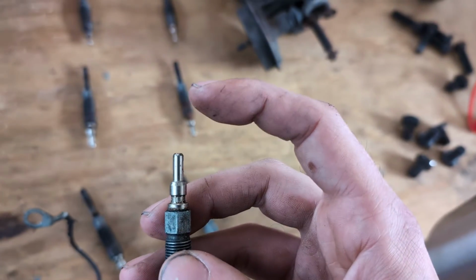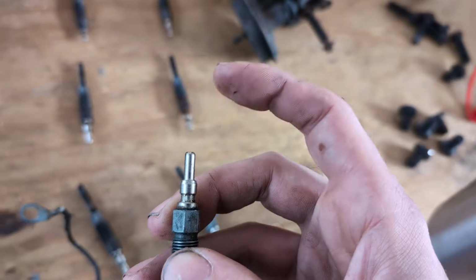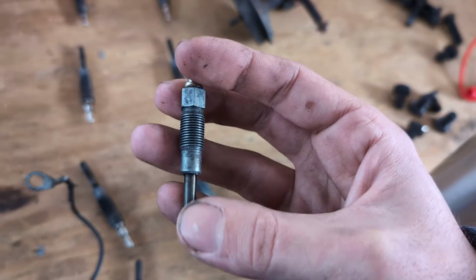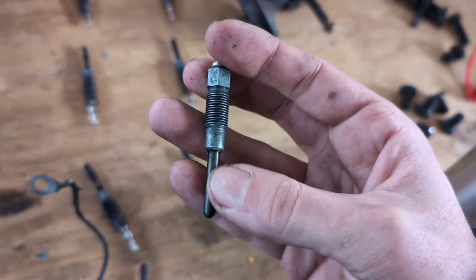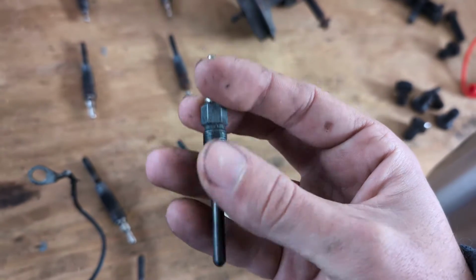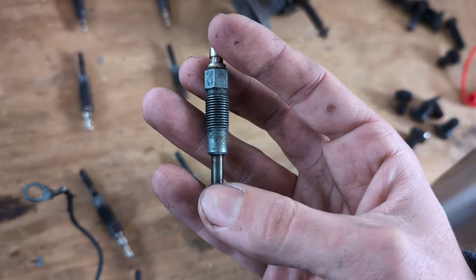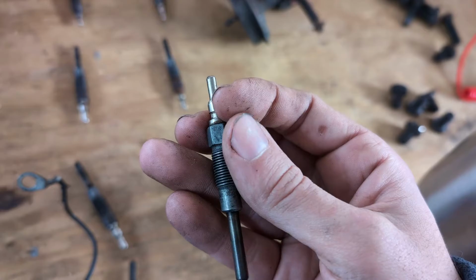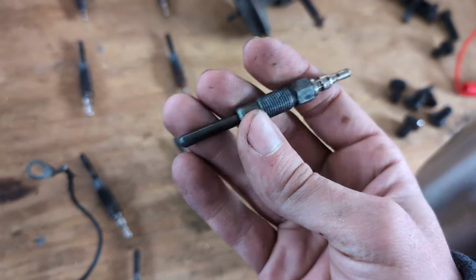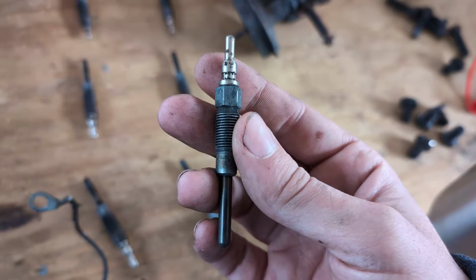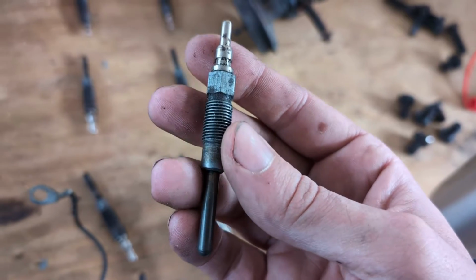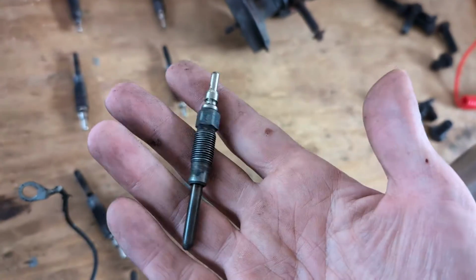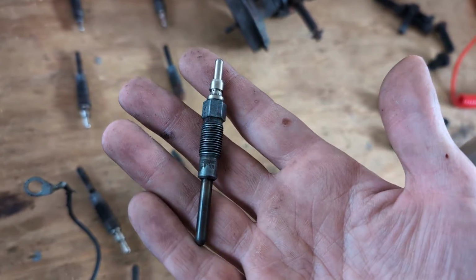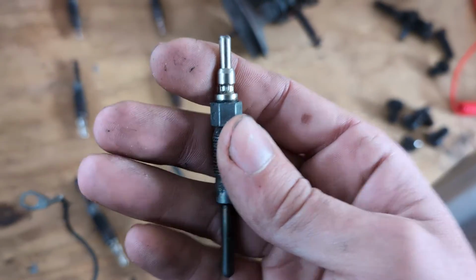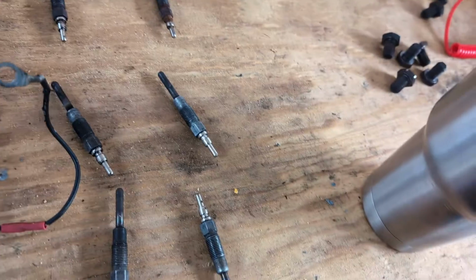So the idea is, if you touch this tip and see 13 volts, there's basically no resistance through the plug. If the plug is bad, with high resistance because the element's busted, you won't see 13 volts because you won't have a ground, and it won't work. Electricity needs a loop — that's how that test works, in case you were curious.